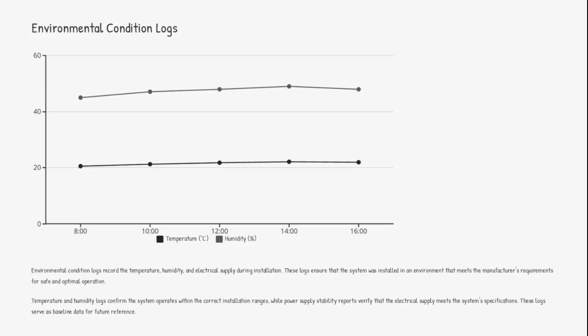Environmental condition logs are crucial for recording temperature, humidity, and electrical supply during installation. These logs ensure that the system is installed in an environment that meets the manufacturer's requirements for safe and optimal operation. They serve as a baseline for future reference, ensuring the system operates within the correct installation ranges.